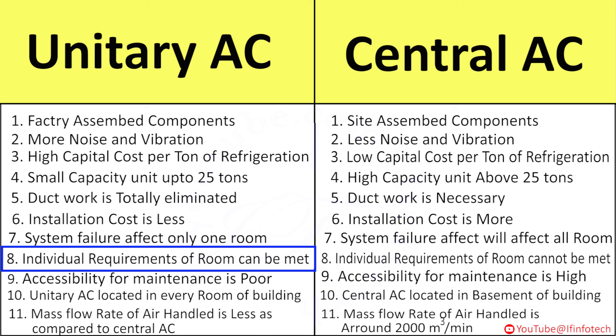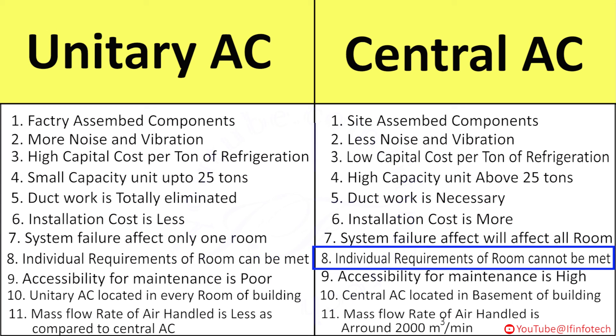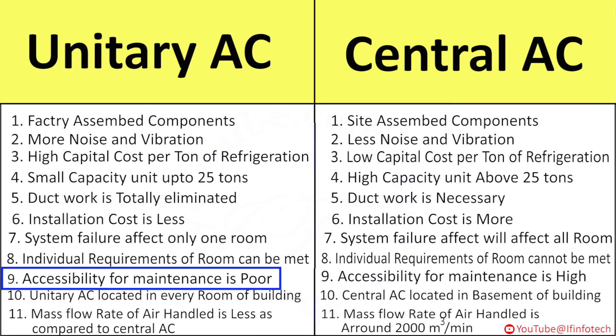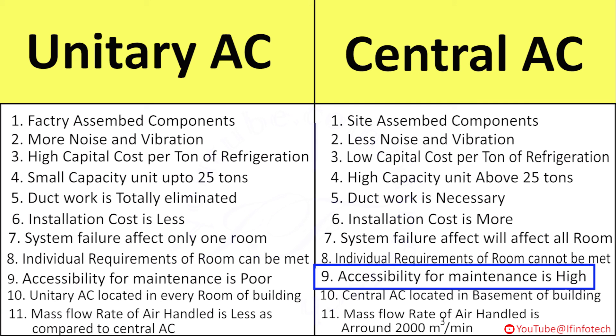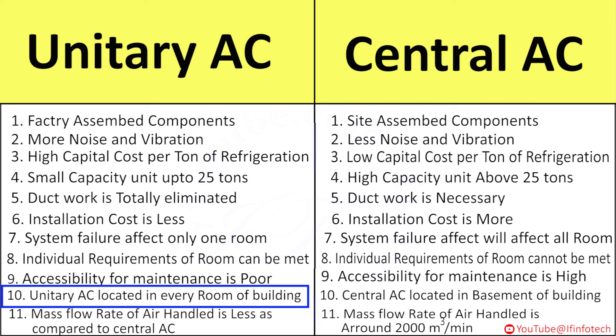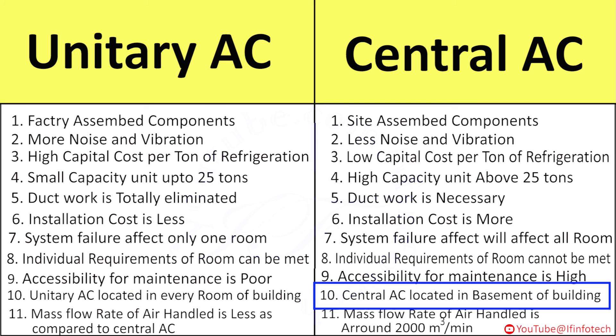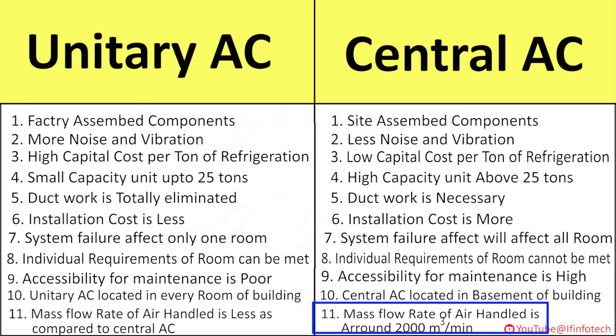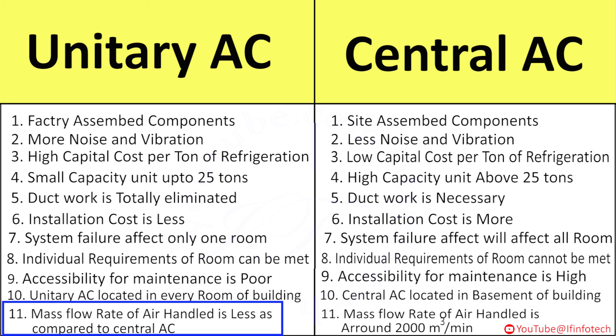In unit AC, the individual requirement of each room can be met, whereas in central AC it cannot. The accessibility for maintenance in unit AC is poorer than in central AC. Unit AC is located in every room of the building, whereas central AC is located in the basement or outside of the building. The mass flow rate of air handled in central AC is around 2000 m³ per minute, whereas in unit AC it is less.